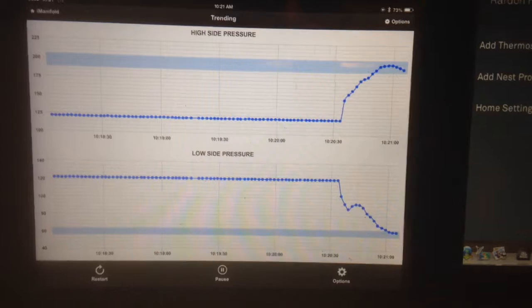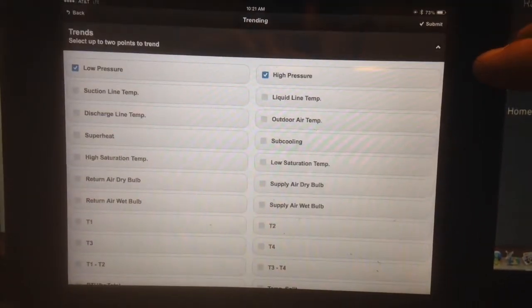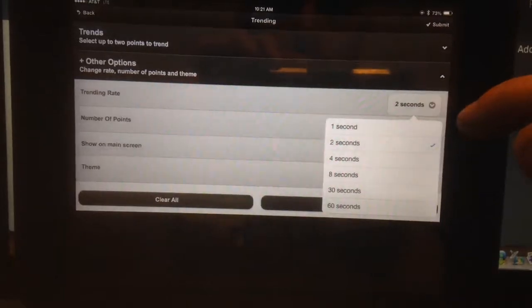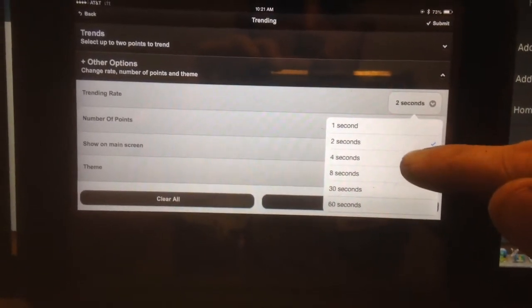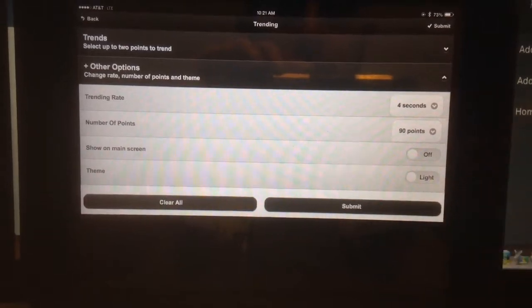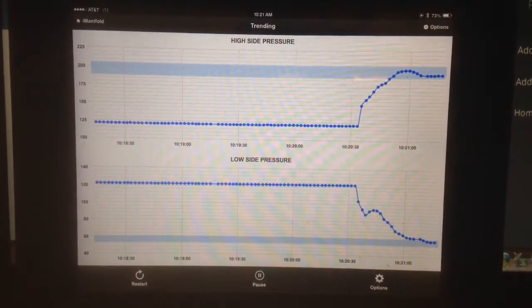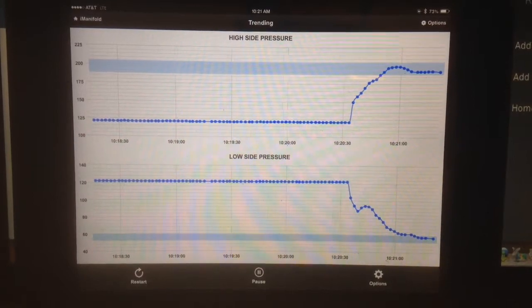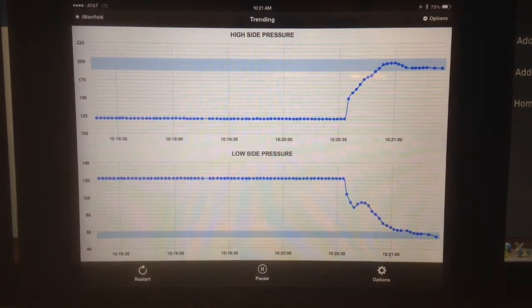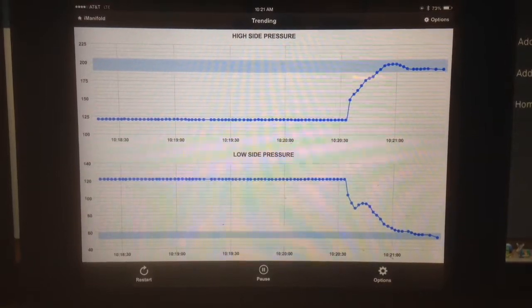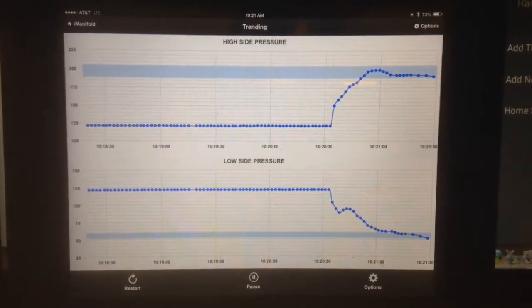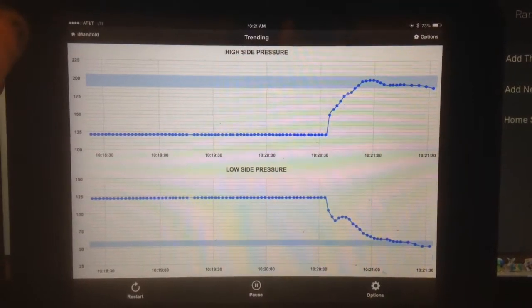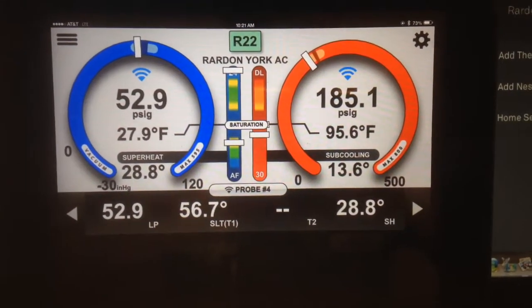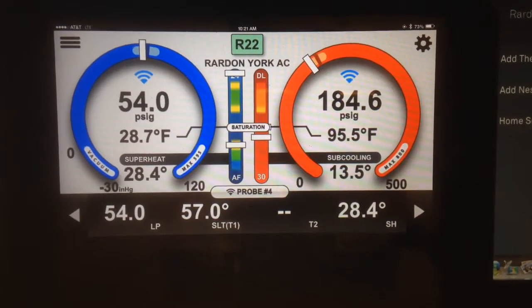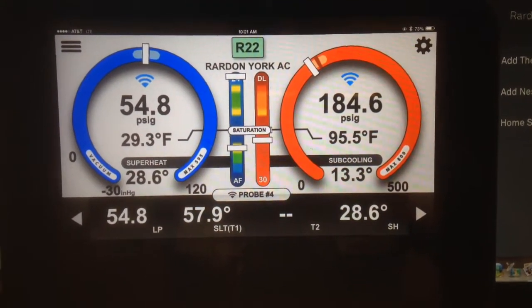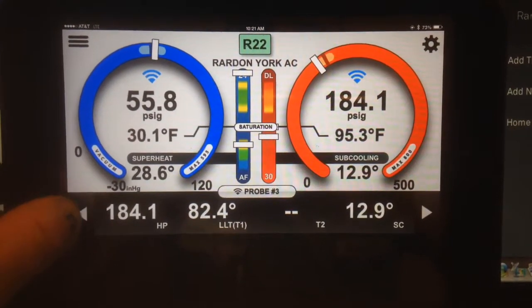Now, if I wanted to, I could go into options and retrend rather than every 2 seconds, every 4 seconds, and that will extend the 90 points to show even more time. It just won't show as regularly. It'll show every 4 seconds instead of every 2. So there we are with that. We're going to go back to the manifold display and watch how the system changes as it runs.